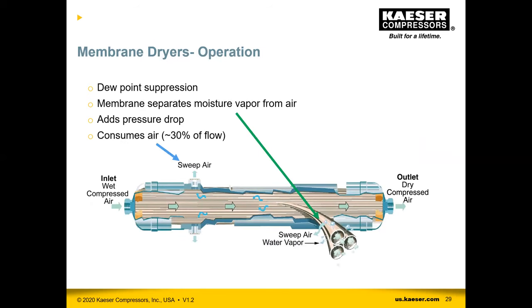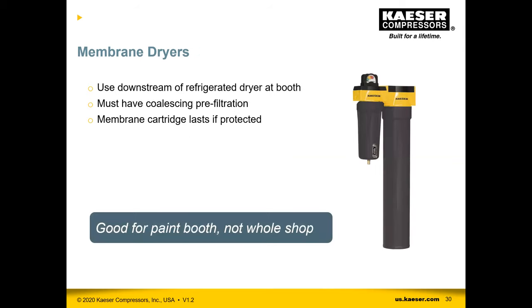Another single-tower option is a membrane dryer. It looks identical to a filter canister but contains a bundle of very fine membrane tubes that allow moisture vapor to separate from air. It does consume a small amount of air and adds some pressure drop. If you have a small application and want to add dew point suppression at the point of use, a membrane dryer is a cost-effective way to do that — great for the paint booth, not for the whole shop. You must protect the membrane from oils or it will not work.